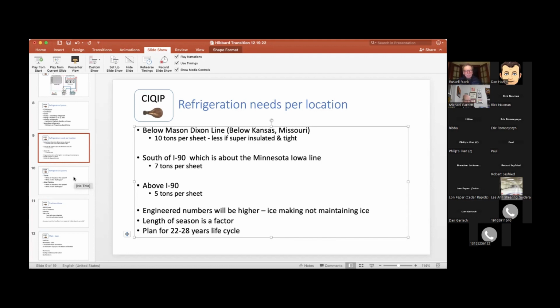Tonnage is most often based on comfort cooling, which is a 44-degree saturated suction temperature. For what we're looking to do, we're running around 5 degrees. It's exactly half. So if you're going to put in a 4-sheet rink, we would spec you no less, depending on where you are, than a 60-ton chiller. That'll give you 30 tons of refrigeration, and that would be 7 tons per sheet.